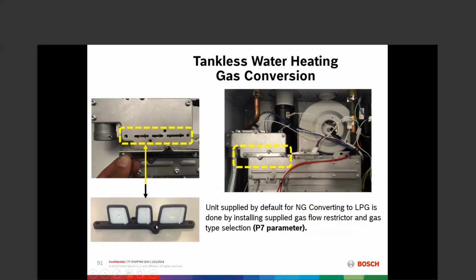The bracket's the same, whether it's 160 or 199,000 BTUs. The orifices are different, whether it's 160 or 199,000 BTUs. So that slides in. You can see that it is witnessed so that we know that we have it aligned properly. It's all witnessed. Slides back in. The 4 number 25 Torx get tightened down. Away we go. Next thing we have to do is go on to the control.